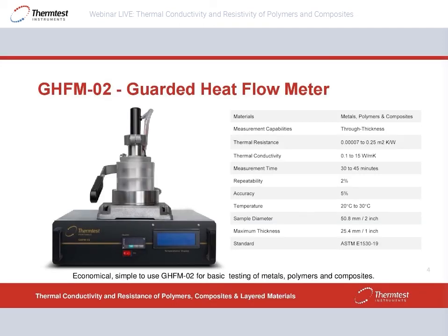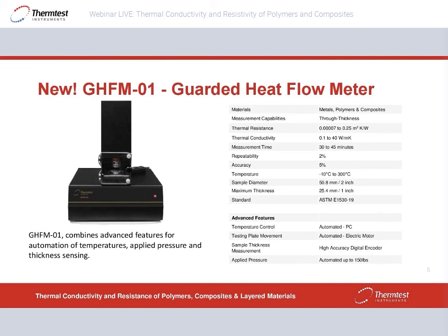The GHFM02 is our portable series following ASTM 1530. There's a new 2019 version of that. A couple keys to pull out of this is it is a simple device for easy room temperature measurement. The new GHFM01, these are the correct specifications for this device. So up to 40 watts per meter Kelvin, -10 to 300 Celsius.